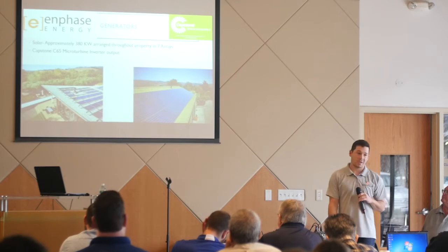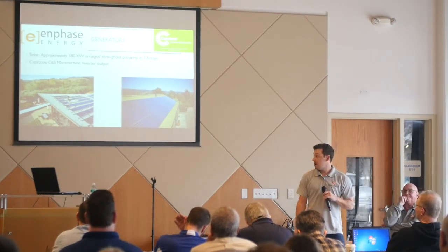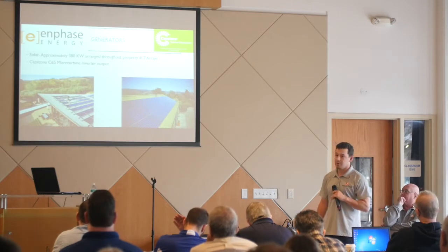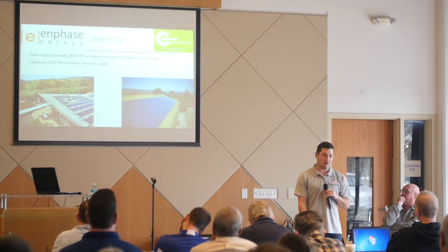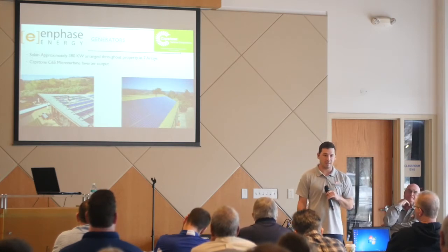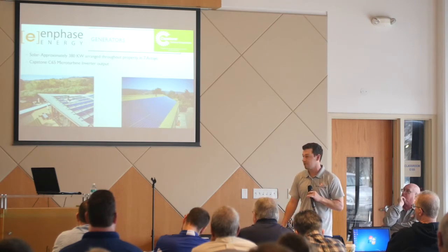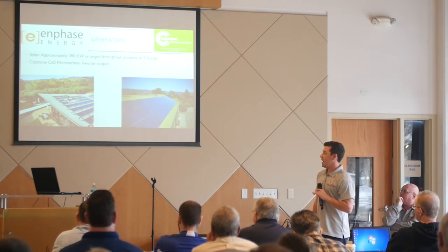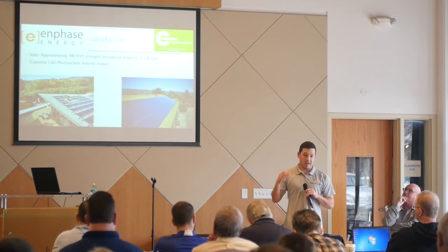So that's running on natural gas. That's our only generator that's non-renewable, the only energy storage or usage that's non-renewable. So when we installed that, PG&E basically threw out our net metering agreement immediately because they couldn't track if the energy that we were exporting was from the solar or from the turbine. So that system is running about 29% efficient by itself.